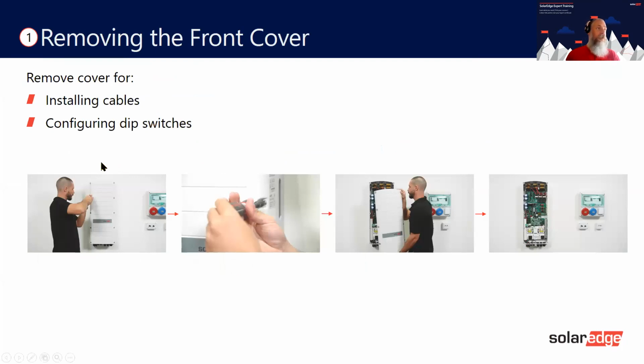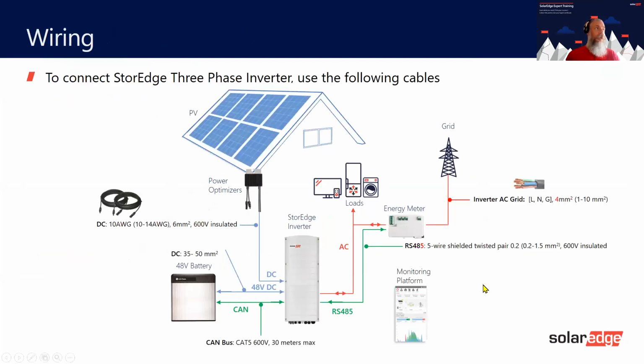The cables themselves, once you've got the inverter on the wall secure, there's also a secure bracket under here at the bottom. Take the cover off, and you can see what's inside. We'll come to what's inside in a minute, don't worry. But basically, we have the RS485 cables, the CAN bus cables, the 48-volt DC, the DC from the roof, and the AC as well.